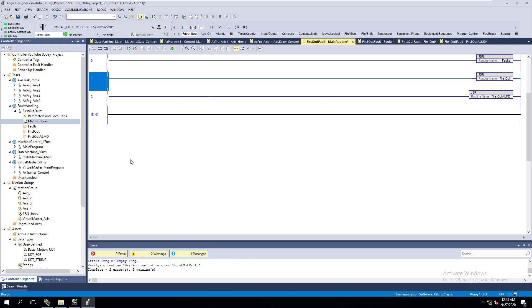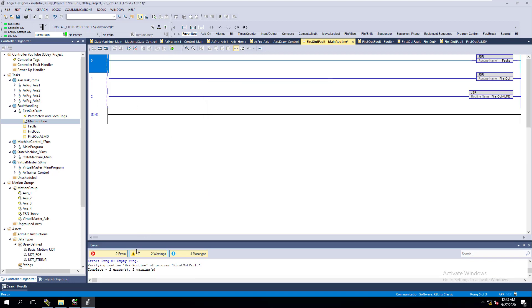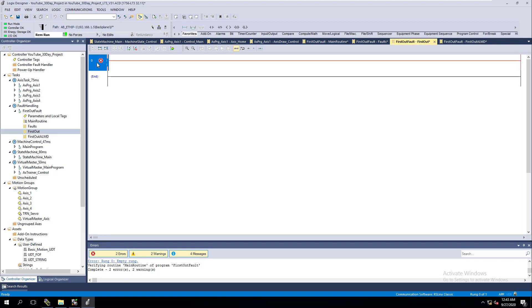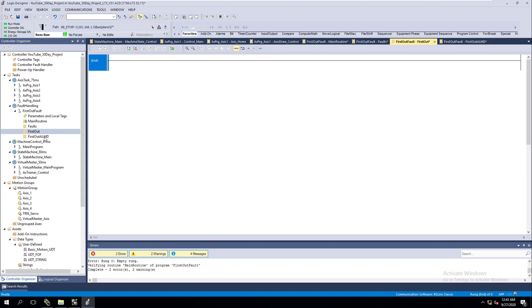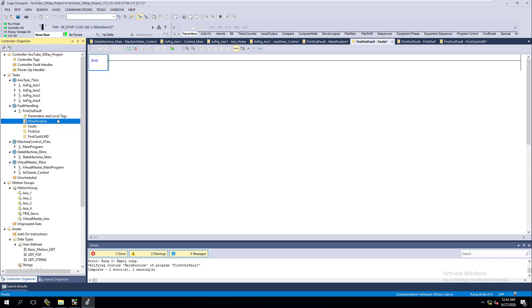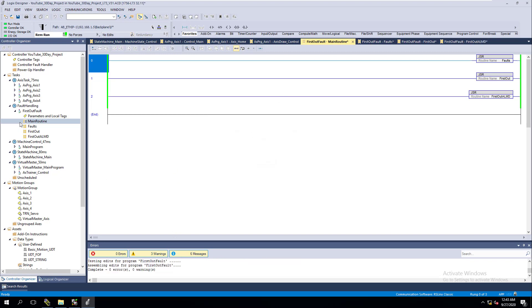In this 10-minute period we've edited and added quite a bit. We have two errors — we have empty rungs. When you open these routines, sometimes they have empty rungs. Let's delete those. Now we have it accepted and everything's in there.